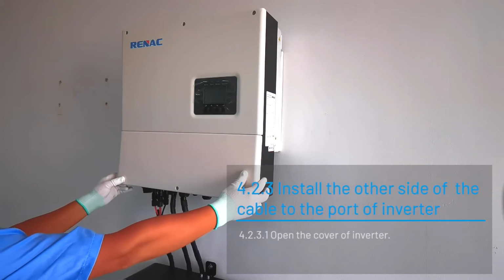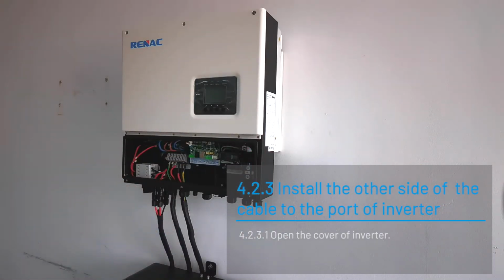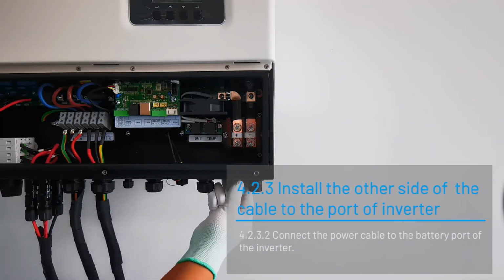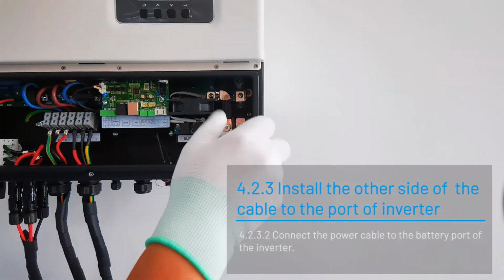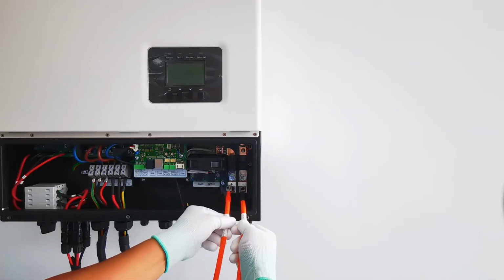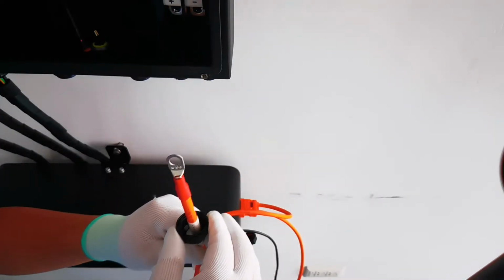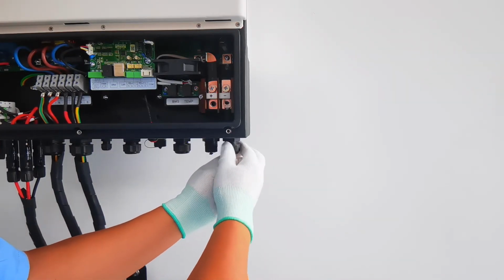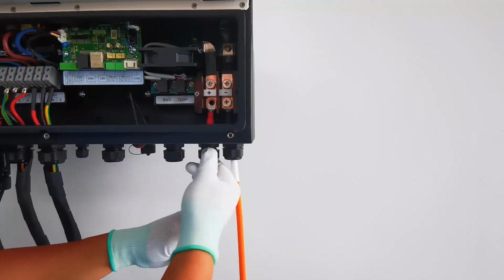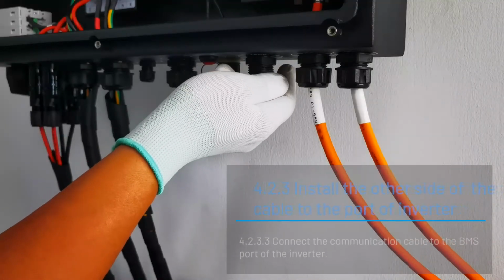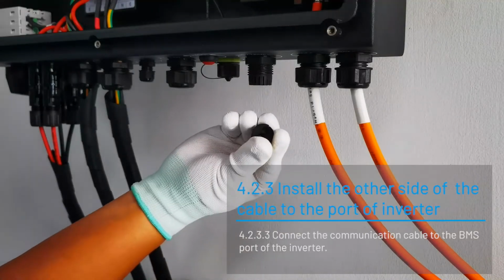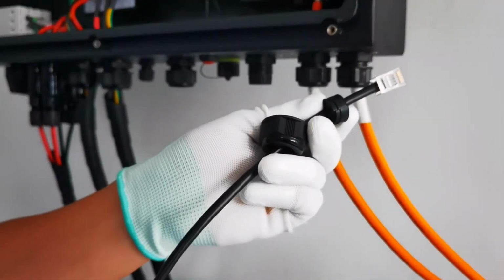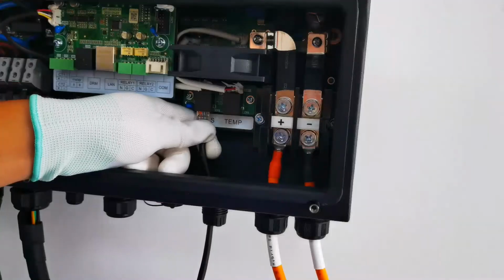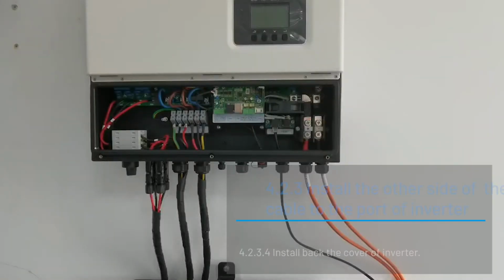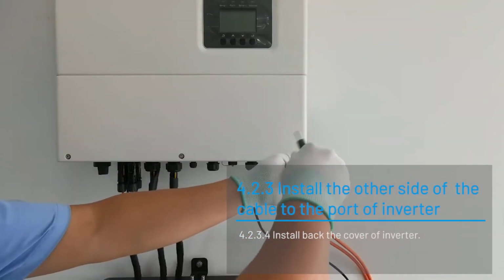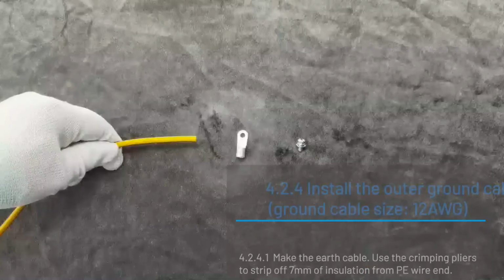Install the other side of the cable to the port of the inverter. Open the cover of the inverter. Connect the power cable to the battery port of the inverter. Connect the communication cable to the BMS port of the inverter. Install back the cover of the inverter. Install the outer ground cable.